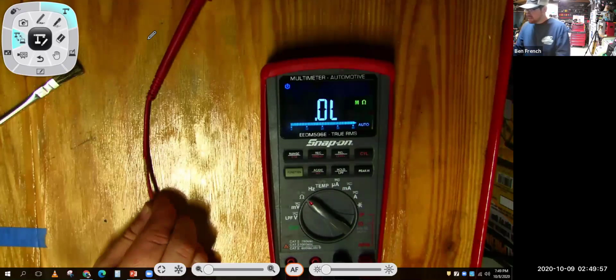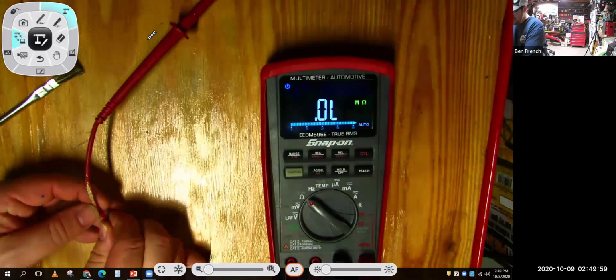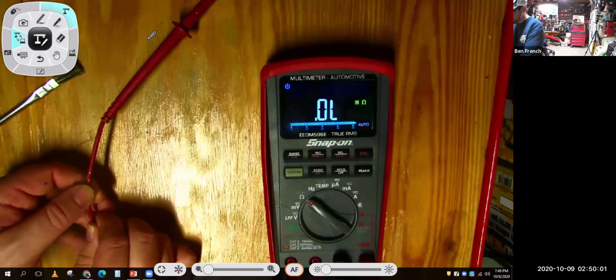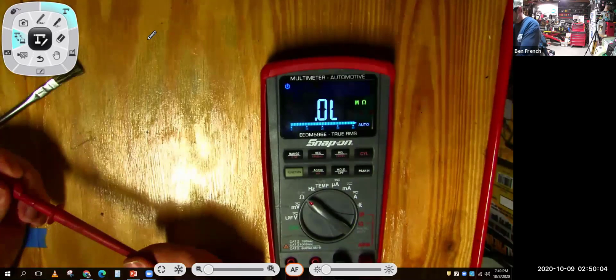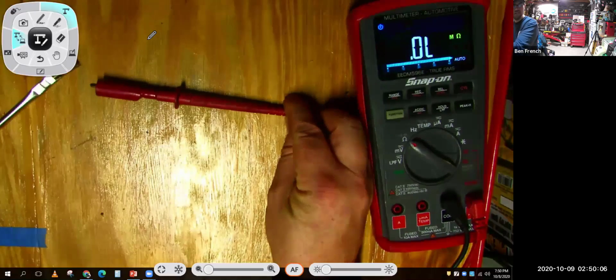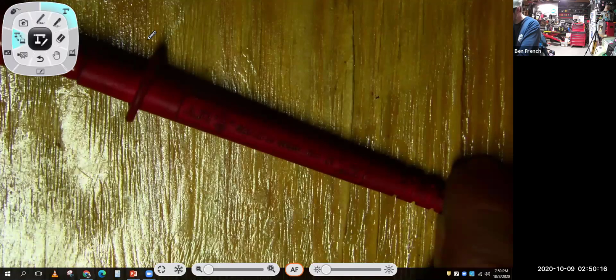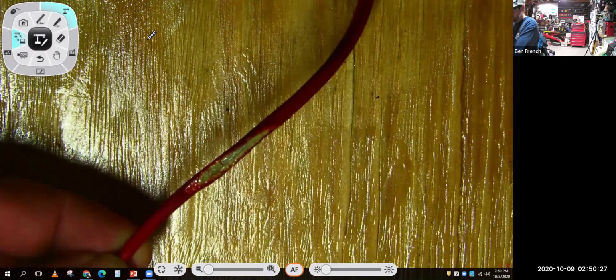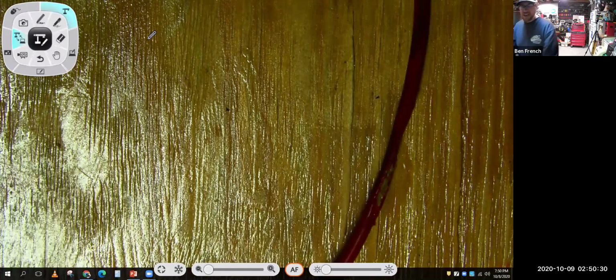This one is melted. The lead still works okay, and the insulation isn't melted all the way through. However, if I zoom in and focus the camera, it says this is a Cat 3 lead that can handle 1,000 volts. Well, guess what? This lead is no longer a Cat 3 lead that can handle 1,000 volts and 10 amps, because its integrity is compromised right here. So check your leads very carefully.